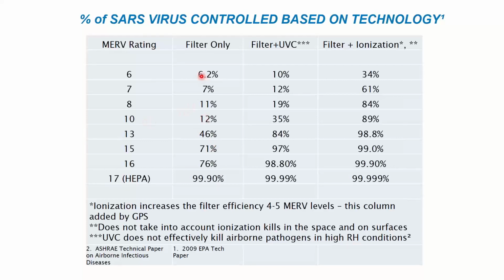Now you can combine that filter with a UVC light, which we talked about in week 1, and get it to perform a little better because now we'll be killing it. I'm not a big fan of putting UVC lights on filters, because once I've caught the thing... UVC lights only do a good job of killing things that are stationary. So if you shine them on a filter, yes. Shine them on a cooling coil, fantastic application, because the coil doesn't move. But trying to use UVC to clean stuff in the air, not so much - it has to wait for the bad thing to land by it.